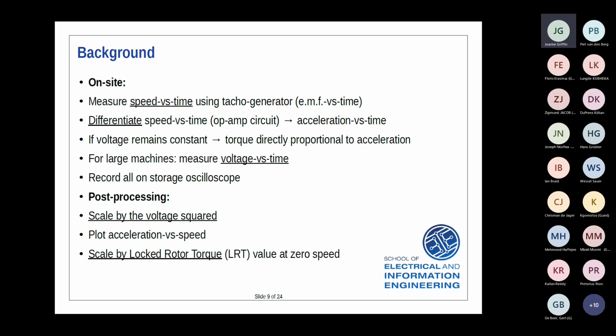What's very important here is the voltage has a significant effect on the results. So the voltage must be kept constant in these tests, or you must measure it and be able to fix it later. The other important thing to note is that the locked rotor torque is obviously at standstill. So as the machine is decelerating, it's stationary for a moment and then it accelerates. We need to know what the torque is at that point so that we can scale it by the locked rotor torque value. That's also critical. And in fact, that's going to become quite problematic later in the presentation.